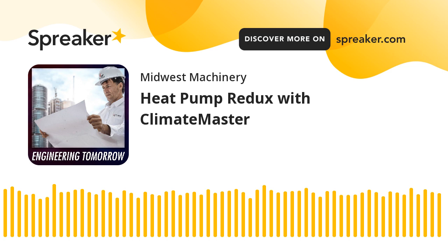In a winter operation, in winter warm-up, let's just say water actually retains the heat rather well overnight. So in an unoccupied time, the system shuts down. There's still going to be some heat in that system piping, but in the morning, most likely in the winter, every zone in the building is going to require heating. So what's happening is, opposite of that summer operation, all the heat pumps are in heating mode. And when they're in heating mode, we're dumping cooler water back into that system loop.